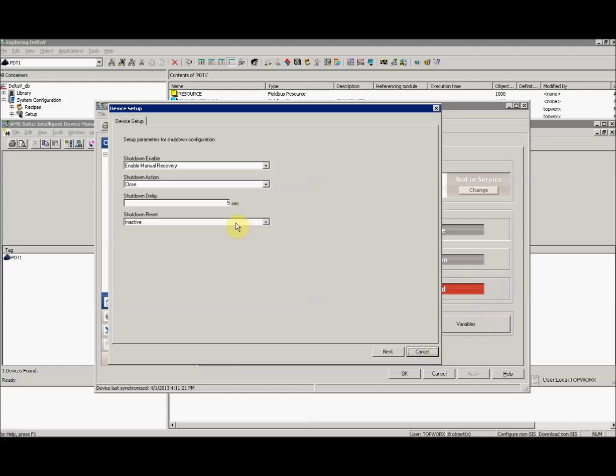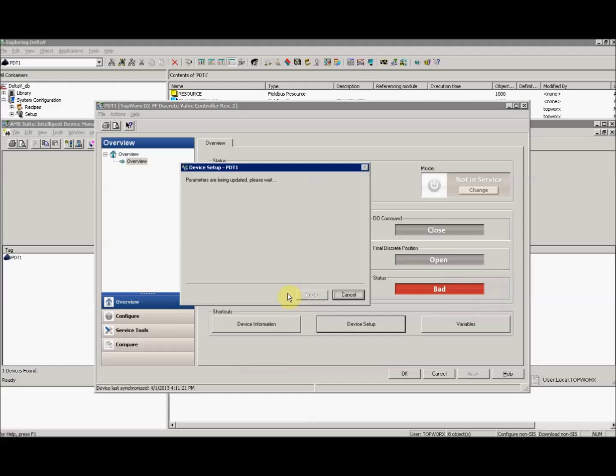This next window is shutdown configuration. Inside the sealed cube, there are two circuit boards, a sensor board and a foundation Fieldbus board, and they are linked by a physical connection. If the cube senses any fault in the integrity of this connection, either electrically or physically, it will enter into this shutdown mode if it's enabled. And this is how you can tell the cube how you'd like to perform, either open or close, if it reaches this catastrophic state. You can also program in a delay, and you can also program in a reset on it as well. So once you get it set how you like, or if not at all, go ahead and click Next.